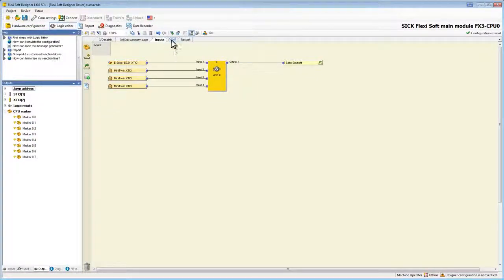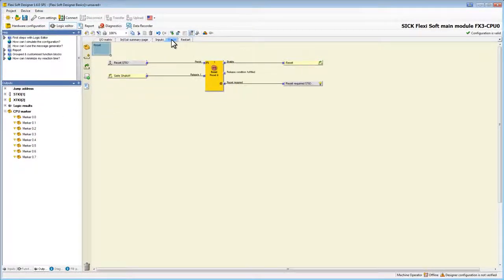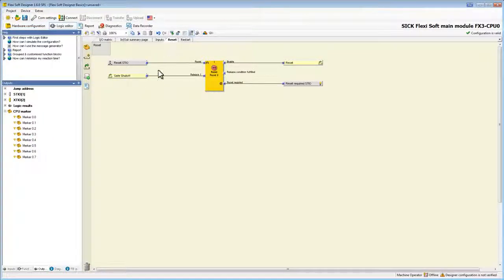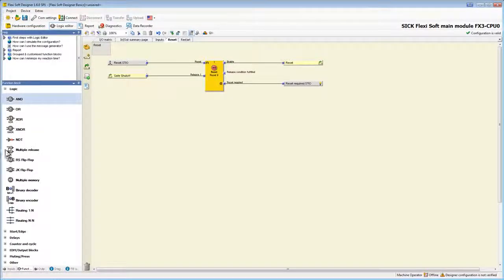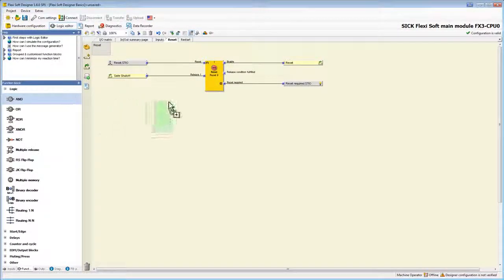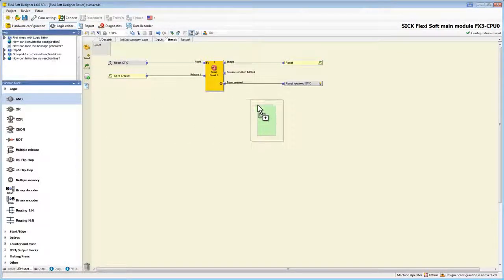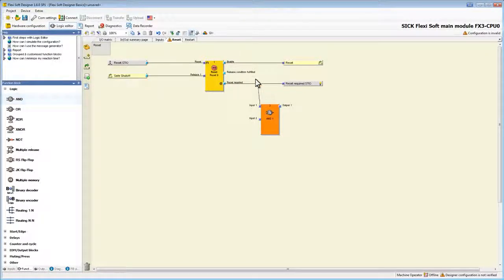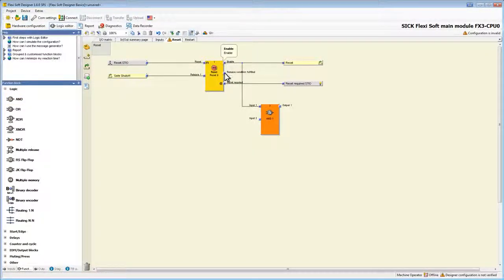In our example application we want another lamp to show us if a reset is required, but contrary to the lamp we already have, we want this one to be switched on permanently as soon as the conditions for reset are fulfilled but the machine hasn't been restarted yet. Therefore we need another AND function block. Now we connect this block with the release condition fulfilled output of the reset block and the enable output.